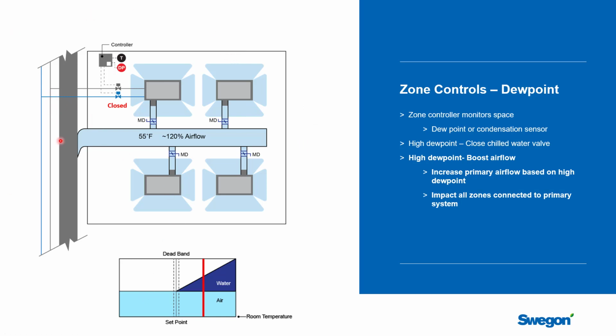And so as you open up this air handling system and start to dry out a larger area, it will help you get that humidity out of the building. So you can close this valve off so that you don't run a risk of condensation. Now you've got high humidity. What you want to do is to flush this area with as much air as possible to dry it out. So this will help as a backup plan to help deal with an unusual circumstance.